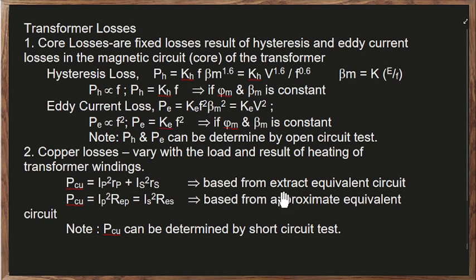So this is the exact equivalent circuit of our transformer. You can also use the approximate equivalent, so I_P squared R_EP or equal to I_S squared R_ES, wherein our R_ES and our R_EP are the equivalent resistances of our primary and secondary winding. So the copper loss can be determined using the short circuit test.